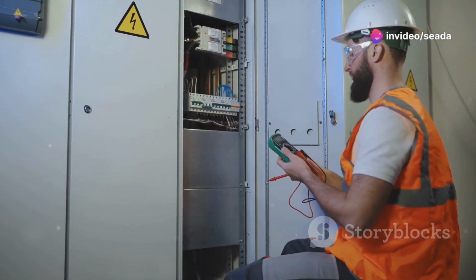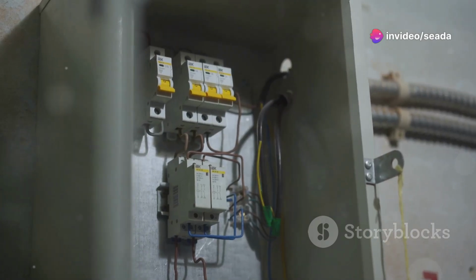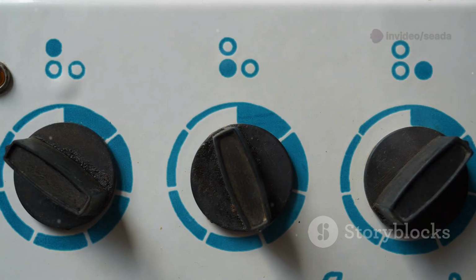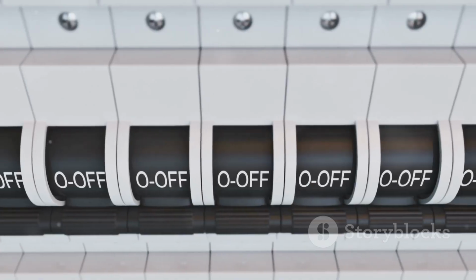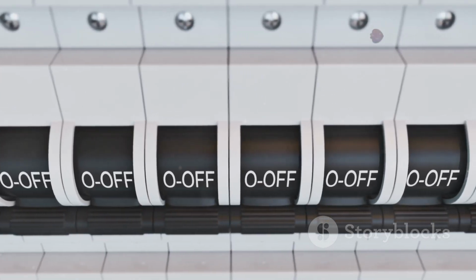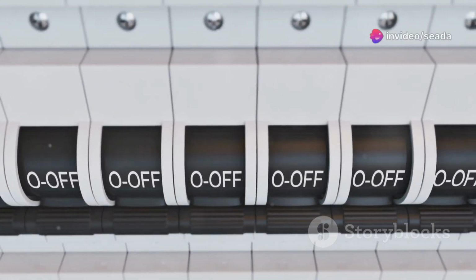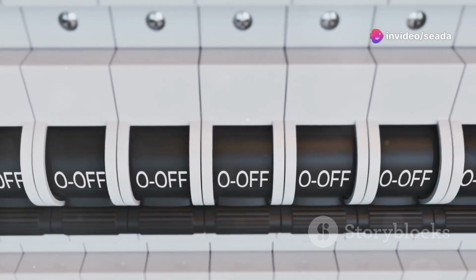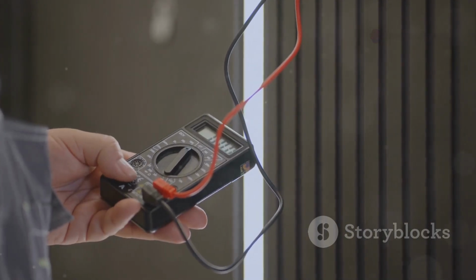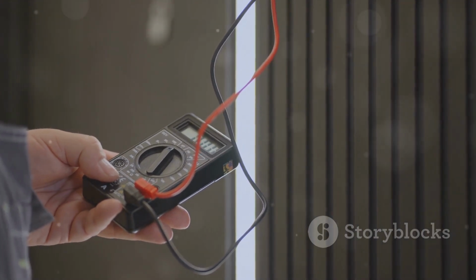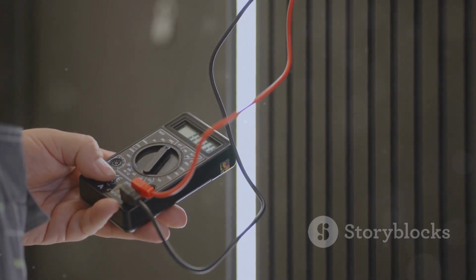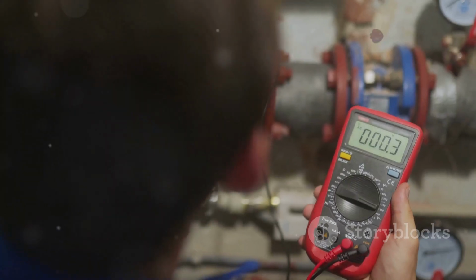Safety is non-negotiable. Always isolate power at the main switch before opening a consumer unit or unscrewing a socket. Use a lockout or tagout. Tape the switch and label it. Danger, do not switch on. Prove the circuit is dead. Test your voltage tester on a live source. Test the circuit, then retest on the live source. This 3-step process eliminates doubt.